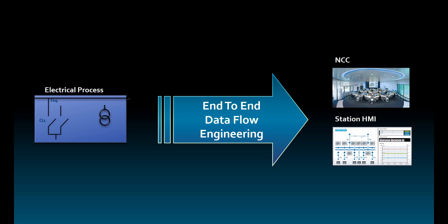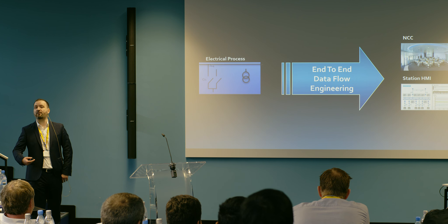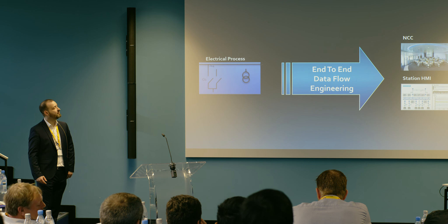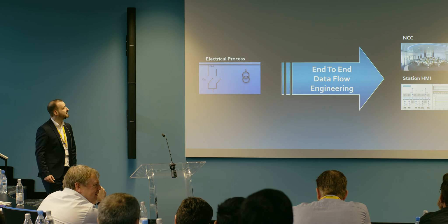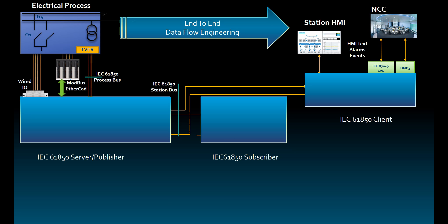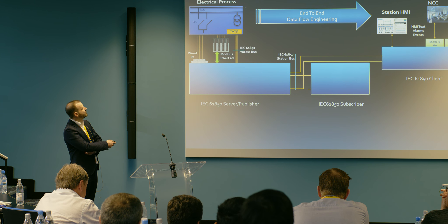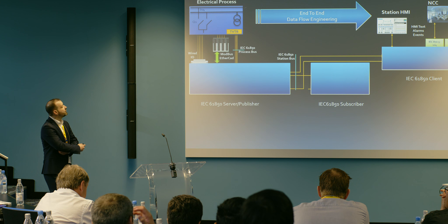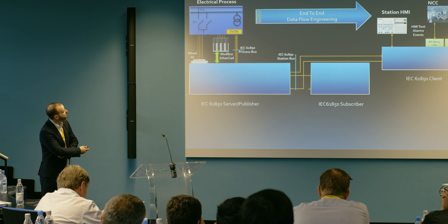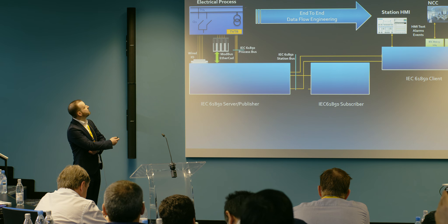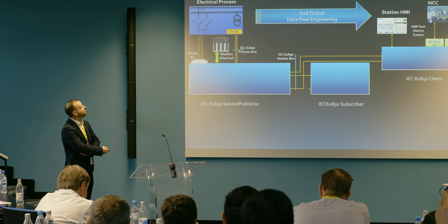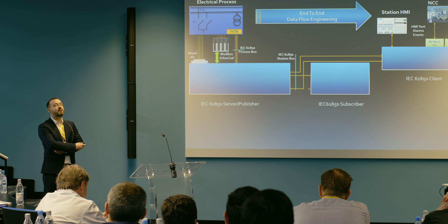On the other side, we have the operators with the displays. They consume information from the electrical process and issue commands that go back to the electrical process. Along this path we can trace the possible routes a signal can take — both at runtime and as part of the engineering process. Our first stop is the IED acting as a server or publisher. We are treating it as a black box, and there are several ways for data to go from the electrical process into the 61850 world.